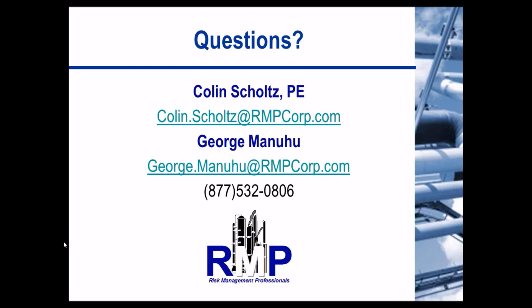Is there anything that you want to add to that, Colin? Yeah, just to add on to that, it's not necessarily required by the standard, but facilities should take lessons learned from their inspections and tests and modify their inspection frequencies as needed. So as George said, condensers typically see a little bit more wear and tear than other things, and so twice a year may be required, or not required, but suggested for some facilities based off their operating experience. And then also, where there are discrepancies between manufacturers' best practices and IIAR, you should always go with the more stringent of the two.